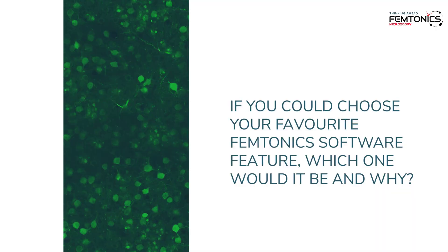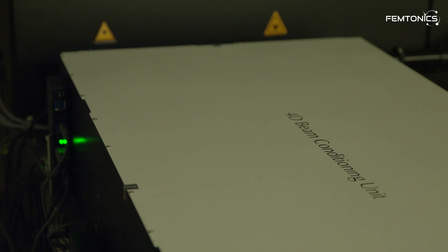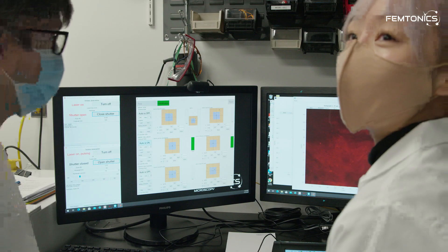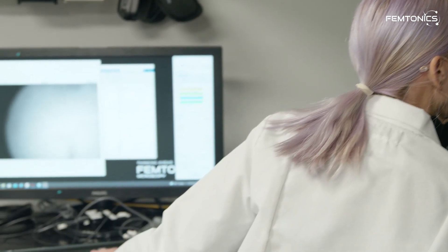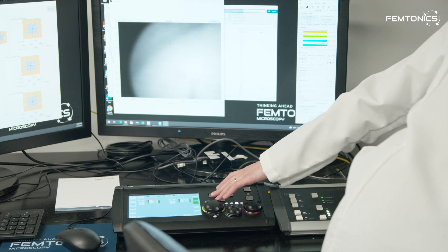If you could choose your favorite Femtonics software feature, which one would it be and why? There's a window that shows you the beam position as it enters the beam conditioning unit. When you turn it on, it shows you in real time the adjustments made to that beam position and you can watch it center on the target position. As someone who's spent really too much time in alignment, I see that in just a second or two and know that what that would mean otherwise is easily 30 minutes to an hour of realignment time. It's not part of the experiment per se, but it definitely makes me happy to see that.